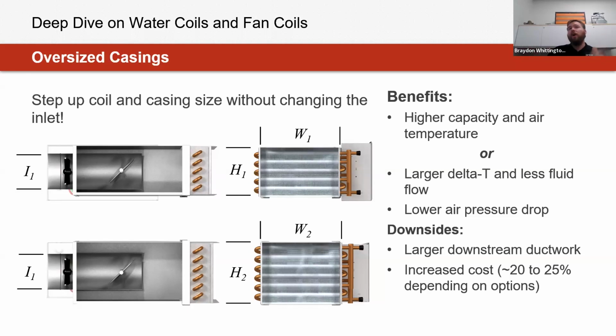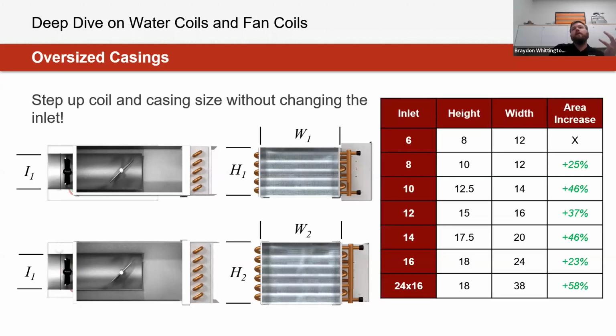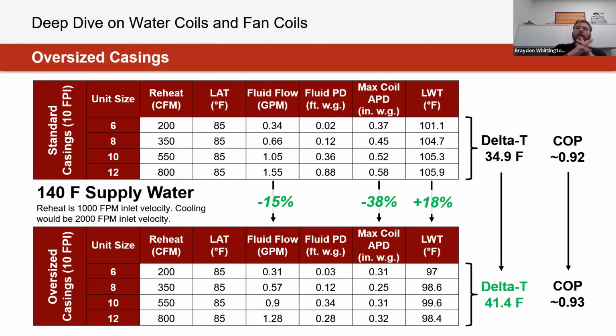Benefit of that bigger coil? Well, we allow for more heat transfer occurring at the coil itself. And from a fluid side, also a larger delta temperature that we're able to provide, with the benefit of a lower air pressure drop. So a good, effective solution, especially in the earlier design phases, for single duct units, or potentially even for utilizing a bigger coil, as you're now able to increase the effective heat transfer area at the coil itself.